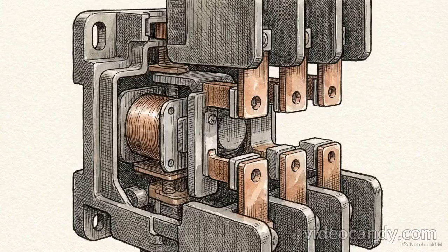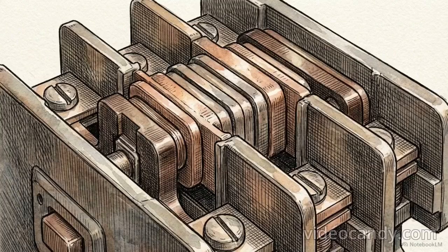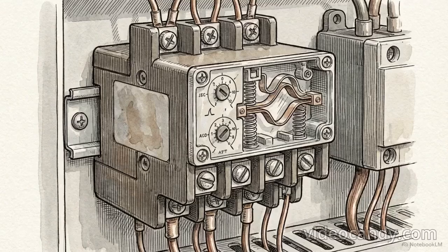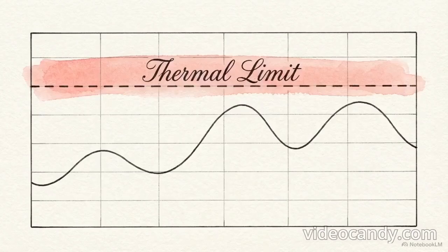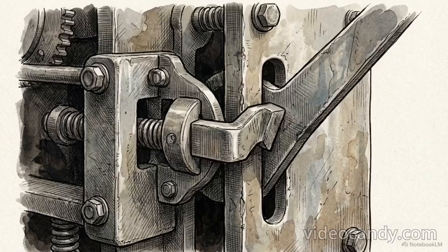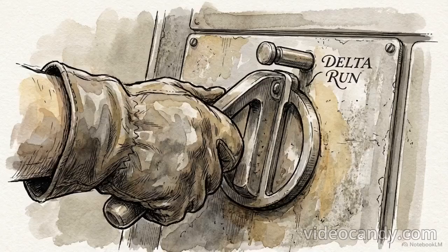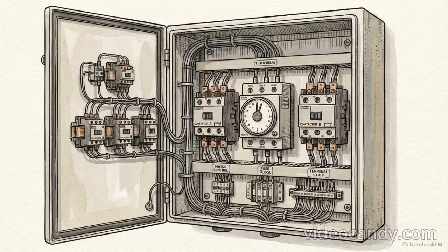A dedicated timer relay monitors this state, physically holding the star connection closed while the rotor slowly overcomes its initial inertia during the run-up phase. Once the timer expires, it initiates a precise mechanical handoff. It opens the star contactor, briefly dropping the motor into an open circuit state before immediately snapping the delta contactor closed. Throughout this entire sequence, the overload relay FT1 monitors the line current, ensuring continuous thermal protection whether the system is drawing 1/3 or 100% of its power.